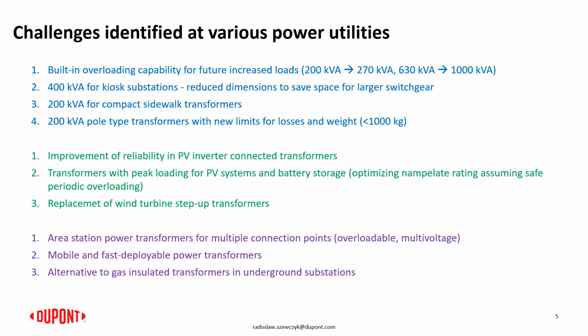The green part of the chart for the renewable generation systems indicates the transformers for the inverter connections in the photovoltaic systems. They need to have the improved reliability, more overloading or more adjustment to the current cycle loads expected in the photovoltaic system. So whether this refers to the photovoltaic systems or the battery storage associated to them, there are possibilities for optimizing the transformer design using the advanced insulation systems for better performance and better cost optimization.